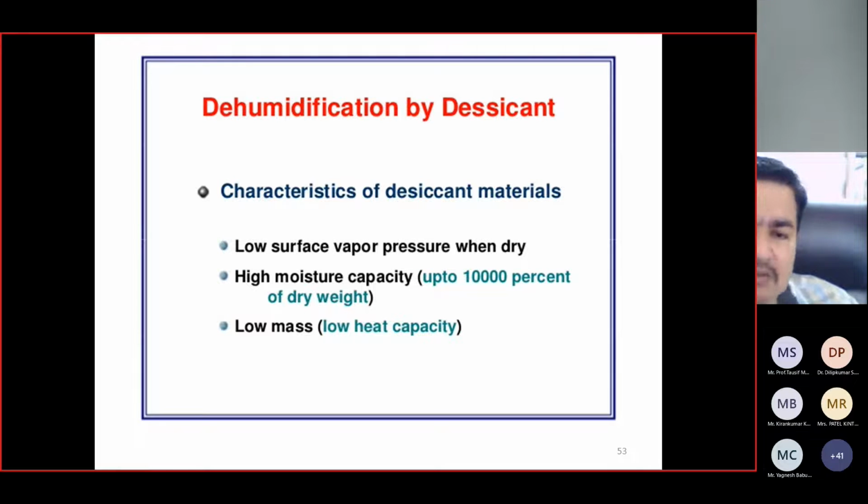That is how moisture travels from the humid air to the desiccant surface, and how we can regenerate it by providing hot air passing over the surface of the wetted desiccant, to be used continuously in the cycle. High moisture absorption capacity: all materials may not be desiccants. A desiccant naturally has an affinity and absorptivity for moisture, and the pressure is the driving force thermodynamically, what we discussed by Dalton's law.